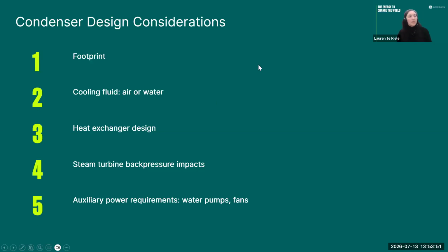We went over it a little bit, but we'll talk more about things you have to consider when designing a condenser. First is footprint - you likely have the awareness that if you're using air, you need a lot more flow than if you're using water for cooling, since water is much more effective at cooling. So when thinking about a heat exchanger between the two, if you prefer air, do you have the space for that?